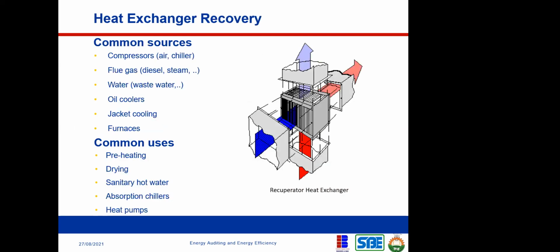So let us look at heat exchanger recovery. What places do you apply a heat exchanger? Now let me make this statement. Remember when I talked about the economizer, when you pass water through your exhaust pipe to recover the heat that is going out through it, what you have actually done is install a heat exchanger around that point. So that water passes through the pipe and extracts the heat from the exhaust pipe. It takes the heat from the exhaust gas and transfers that heat to the water, right? And that's the function of a heat exchanger. That is exactly what is happening in this diagram that you're seeing here. I just thought I should also make that explanation.